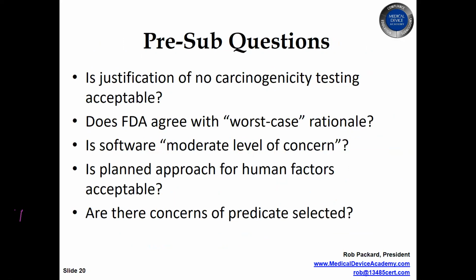Pre-sub meeting questions. One of your questions that you might ask is, a justification for no carcinogenicity test, is that acceptable? Oftentimes, in particular with biocompatibility, they're actually changing the standard. They're rewriting it; a draft is already available for download. They are changing it from being, here's the standard test that we expect, to we ask for physical and/or chemical characterization, and all the other tests are optional based on your biological evaluation. So they're changing completely the way they're approaching it, and probably 80% of your submissions for implants are getting out of these carcinogenicity and genotoxicity tests because they're doing chemical characterization instead, and doing a biological evaluation report showing why those tests aren't necessary based on that chemical characterization.